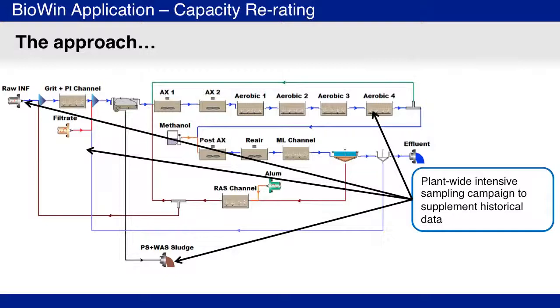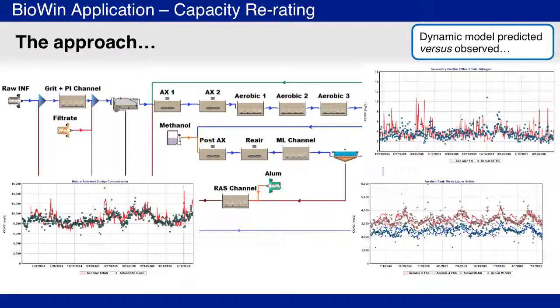After setting up the BioWin flow sheet and incorporating all operational aspects, the model was calibrated to two years of time-varying performance data. In order to accomplish this, a supplemental plant sampling campaign was conducted to augment the existing dataset. Minor adjustments were made until the model predictions matched the observed plant responses for a variety of parameters.